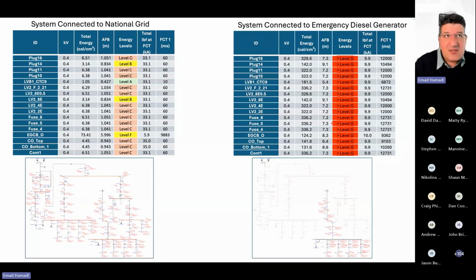I've seen on some sites that they do the arc flash study only for the main source of power and omit the other sources like the diesel generator, just assuming that the higher fault level will end up with higher incident energy, which we know is not true all the time.